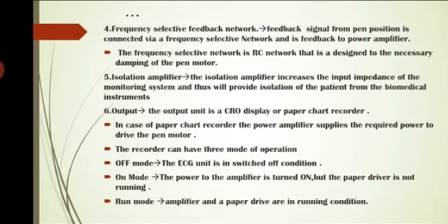Fifth, isolation amplifier. The isolation amplifier increases the input impedance of the monitoring system and thus will provide isolation of the patient from the biomedical instruments. Sixth, output unit. The output unit is a CRO display or a paper chart recorder. In case of a paper chart recorder, the power amplifier supplies the required power to drive the pen motor.